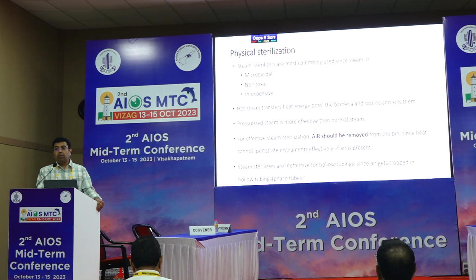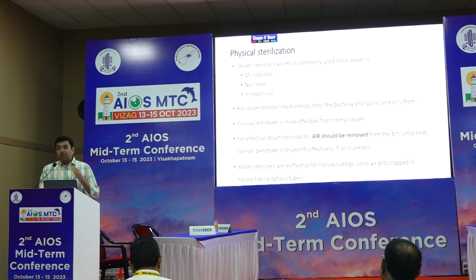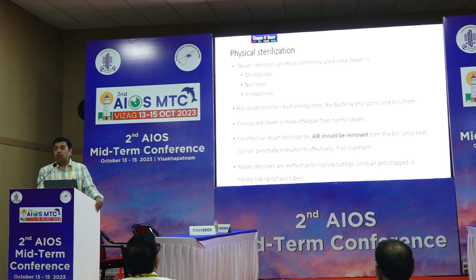Steam sterilizer is the most common type of sterilizer in physical sterilization, because steam is microbicidal, non-toxic, and inexpensive. So how does a steam sterilizer work? A steam sterilizer works by transferring the heat energy onto the bacteria and killing them. Pressurized steam is more effective than normal steam. One very important thing about steam sterilizers is air. If it is present in the sterilizer, it hampers your sterilization process. So you have to take a sterilizer with an air removal mechanism, so that the heat gets transferred onto your wrapping or bin.